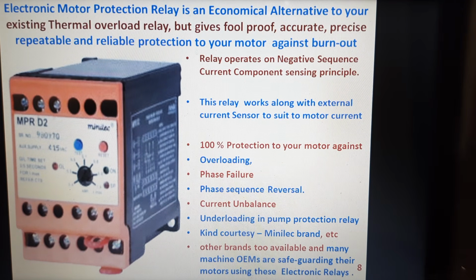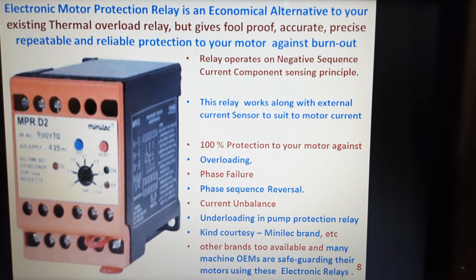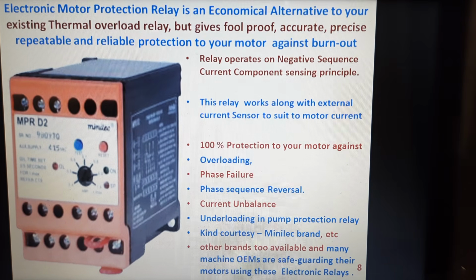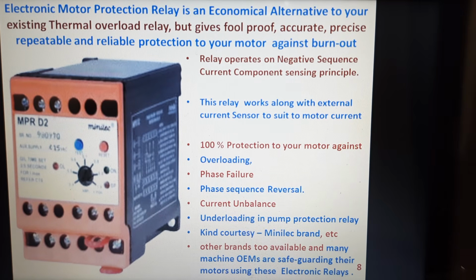The electronic motor protection relay is an economical alternative to your existing thermal overload relay, and it gives foolproof, accurate, precise, repeatable and reliable protection to your motor against burnout. The relay operates basically on the negative sequence current component sensing principle. This relay works along with an external current sensor to suit the motor current. It gives 100% protection to your motor against overloading, phase failure, phase sequence reversal or current unbalance, or, in the case of a pump protection relay, even underloading.